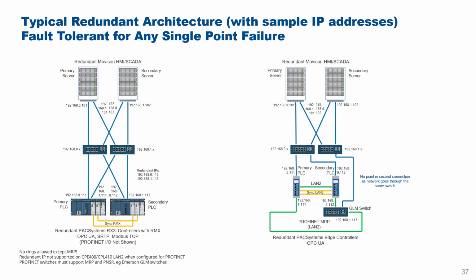And one of the reasons that's important is, certainly when you want to go to fault tolerance on the Profinet network, you can do that with an MRP ring. But as soon as you've got a ring, then that means that normal network operation is very complicated. So it would be very difficult to mix this architecture on the left with a Profinet MRP ring.